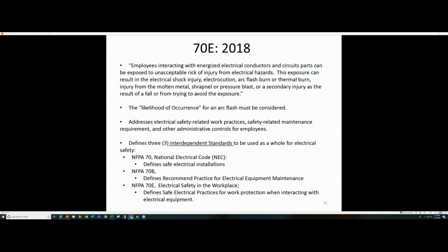Now, there are actually three standards in the United States that define, and they're interdependent as a whole, electrical safety. The first is NFPA 70, which is what we call the National Electrical Code. That defines safe electrical installations. So all your different fusing and breakers and loading and protections and all that is NFPA 70. NFPA 70B defines the recommended practice for electrical equipment maintenance.